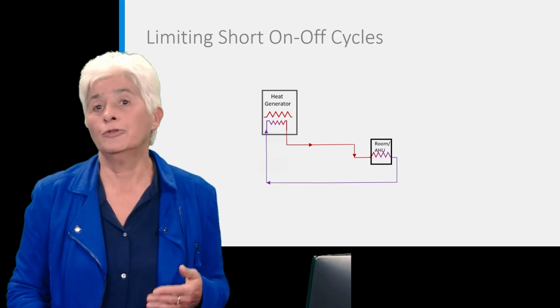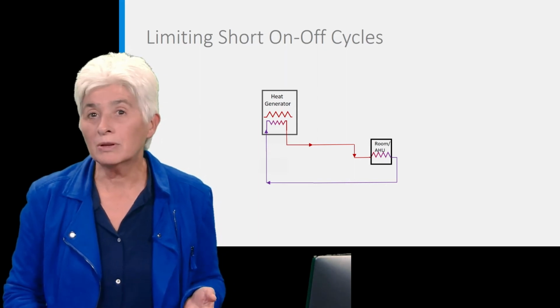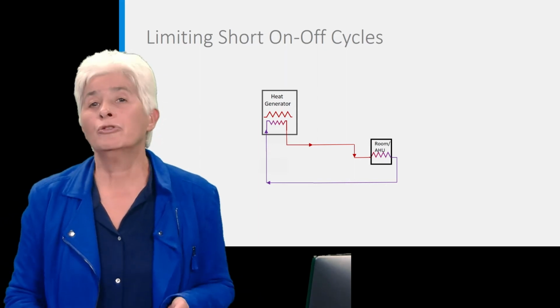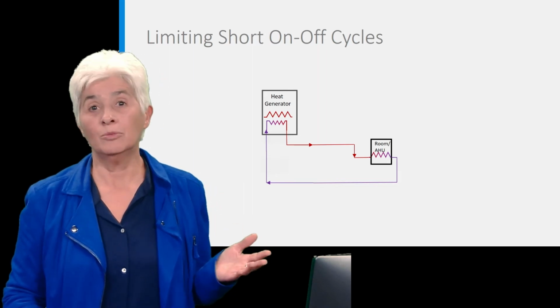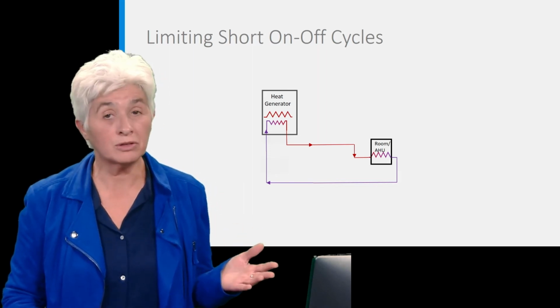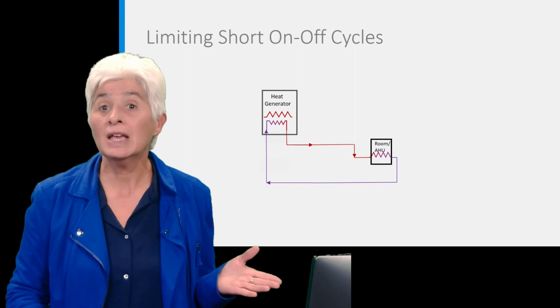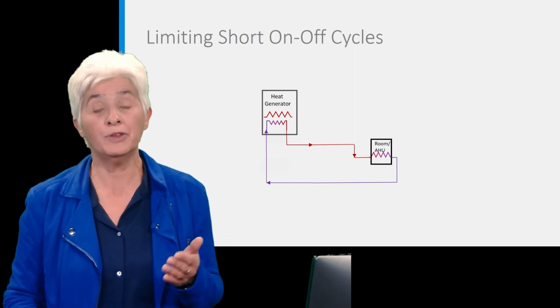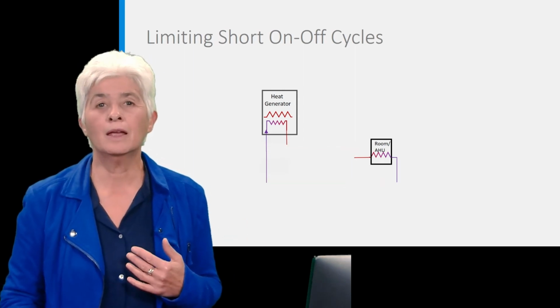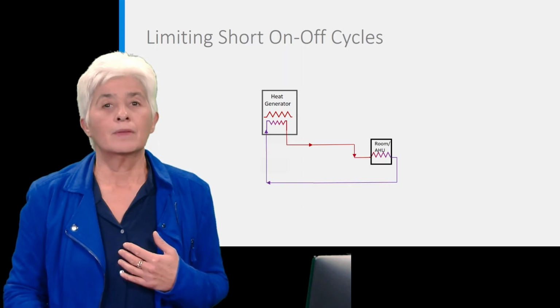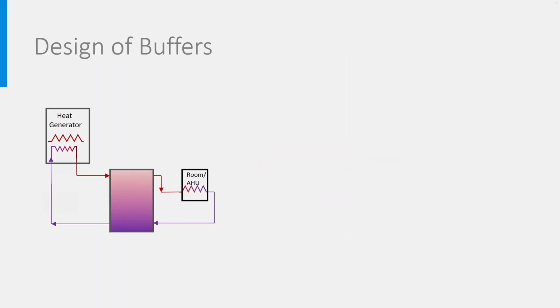This is not great for the mechanical equipment like the pumps and the valves. Most gas boilers can cope with that, but with heat pumps and their compressors, that may give more problems and decrease the service life of the equipment. And that is a good reason to place buffers between the heat generator and the emitter. A buffer is just a water tank filled with hot water where heat from the generator is stored.